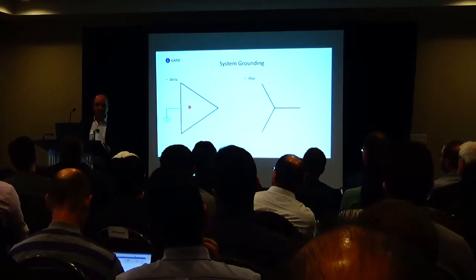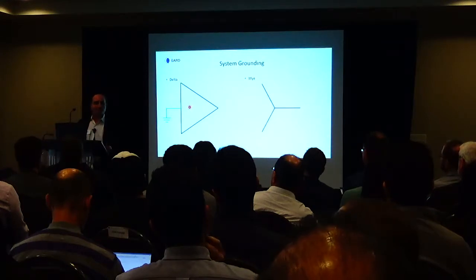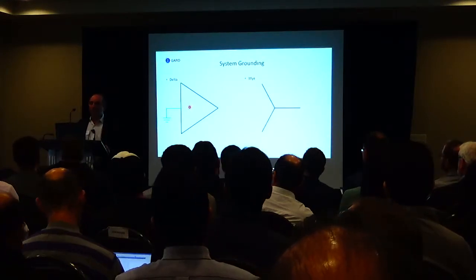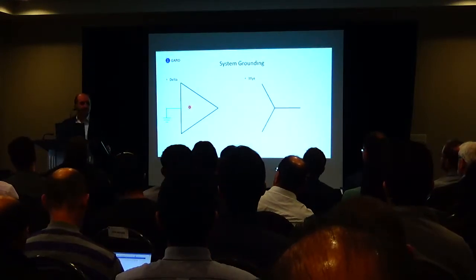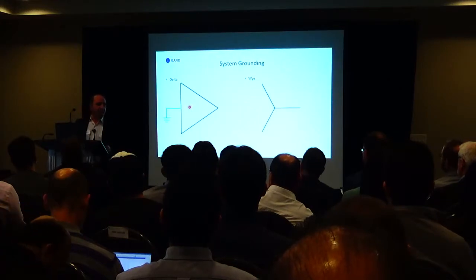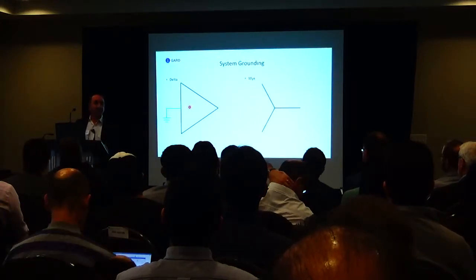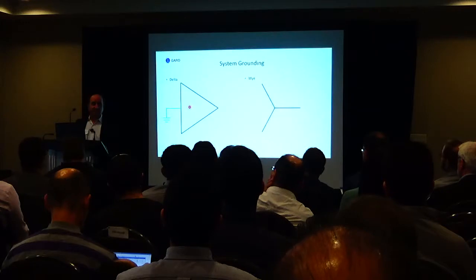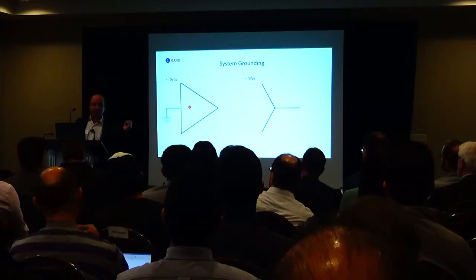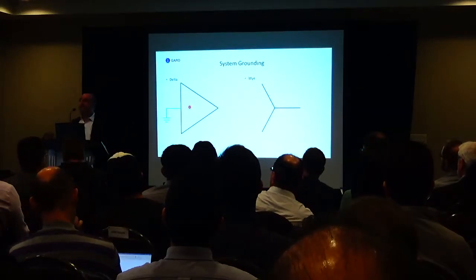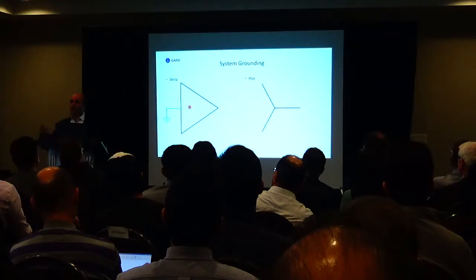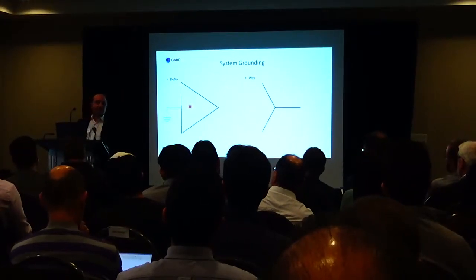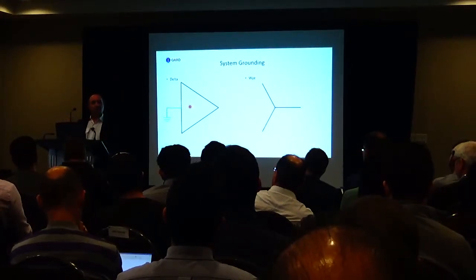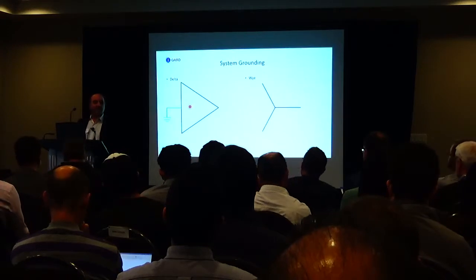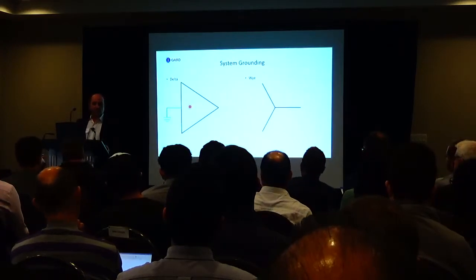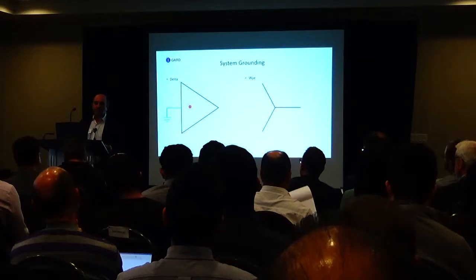208. Exactly. So you're an electrician, you're measuring 120 volts to ground on two phases, 208 to ground on the third phase, and 240 volts phase to phase. What do you think you have? You have this. But you have to recognize that you have this. So when you go into a facility and you're measuring voltages, you have to understand what the grounding system of that is before you start making your measurements, so you understand what you have.